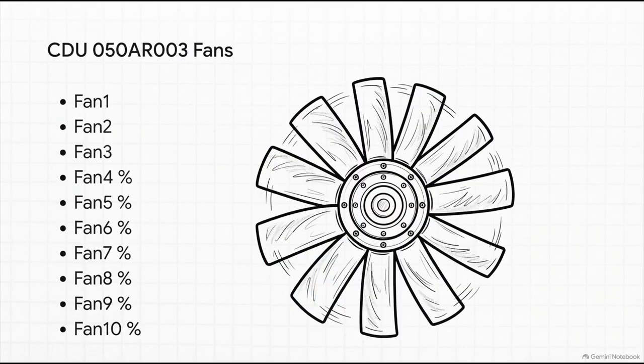To really put that level of precision into perspective, just think about your laptop or home computer for a second. It probably has one or maybe two internal fans. Well, just one of these industrial CDU units, Unit 050AR003, requires 10 independent fan percentage sensors just to breathe, fan 1 through fan 10, all continuously monitored and modulated. This is brilliant because it means if even one fan starts to underperform, the other 9 can dynamically compensate on the fly to keep that coolant flowing without even a single degree of temperature fluctuation.